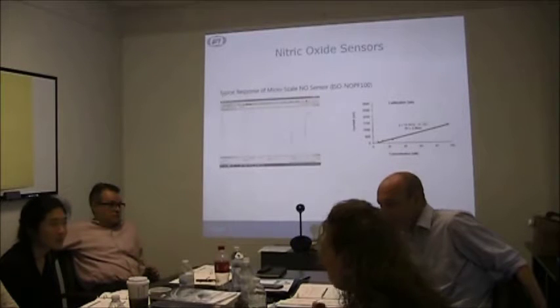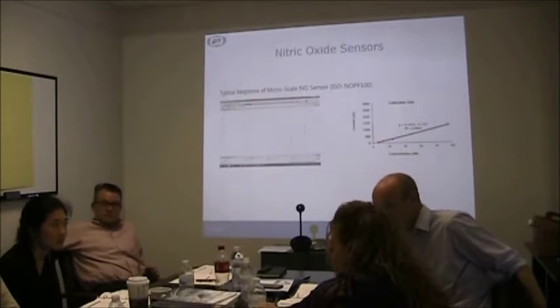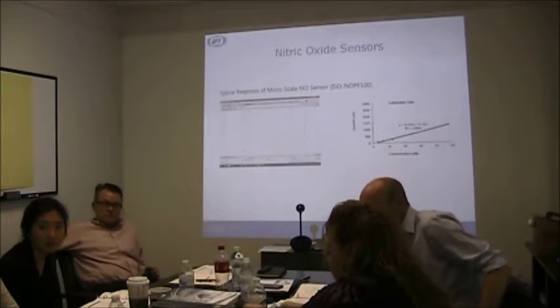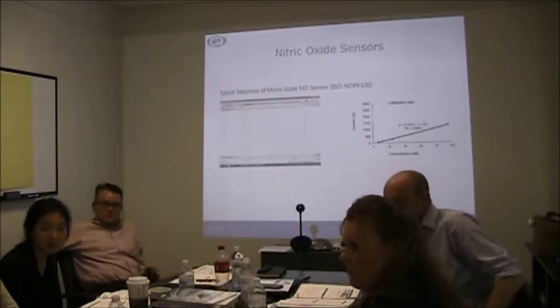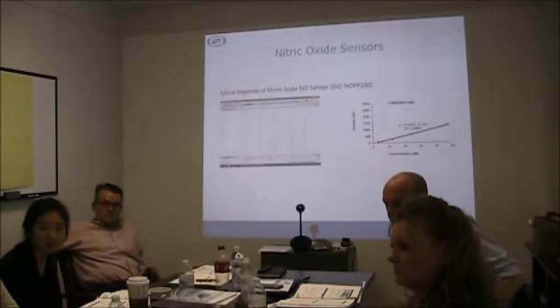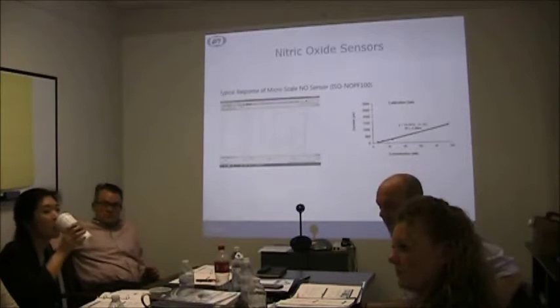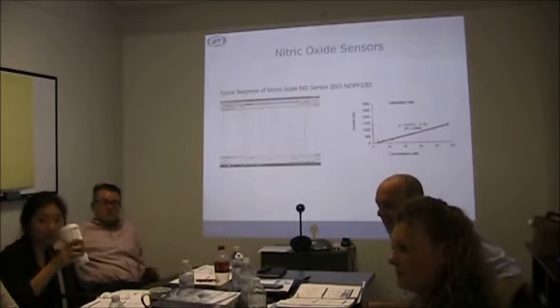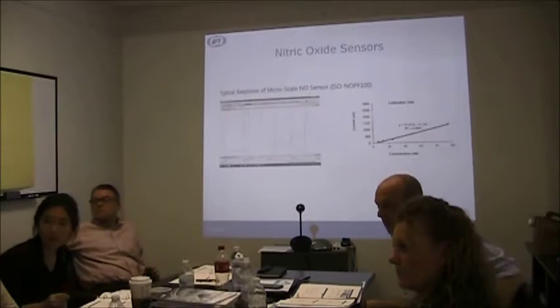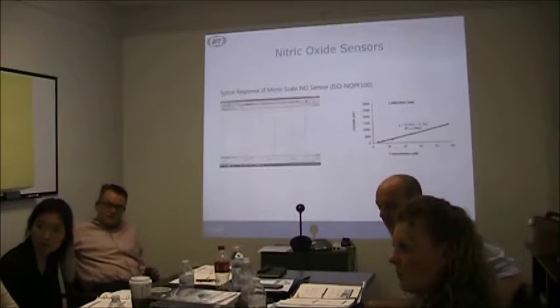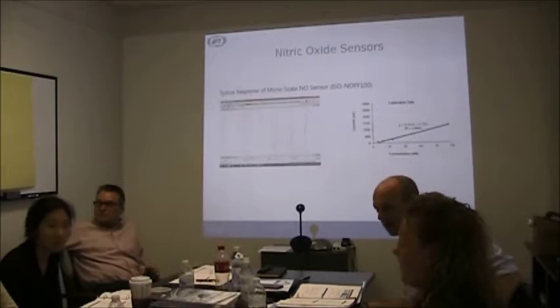Does it need heating time before you do the calibration? Do you need to soak it in the solution? All our sensors have pre-set polarization times for stability. For the F100, it's usually a few hours. For the 2mm ISONOP sensor, it's 8 to 12 hours. So it takes 8 to 12 hours for it to stabilize, and then I can take a measurement? Correct.